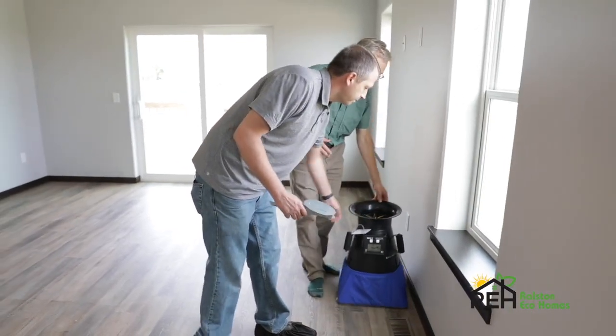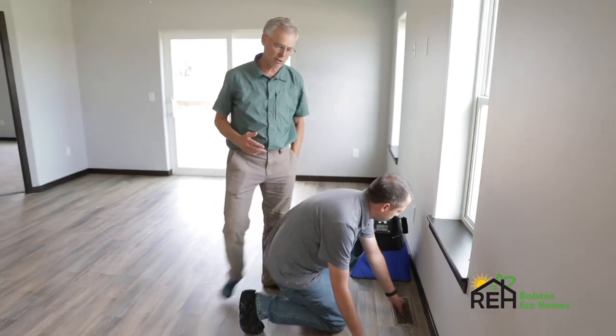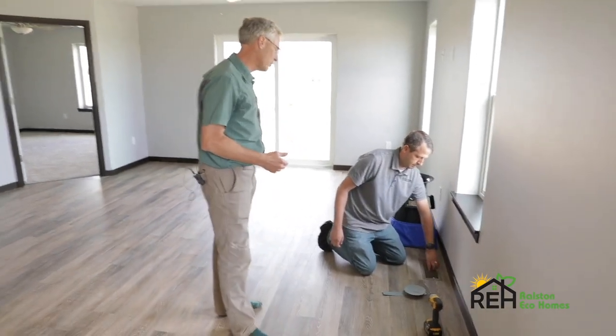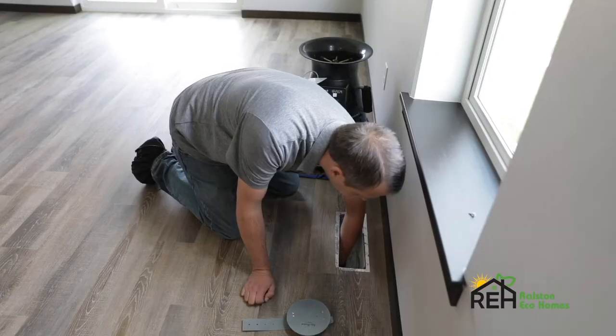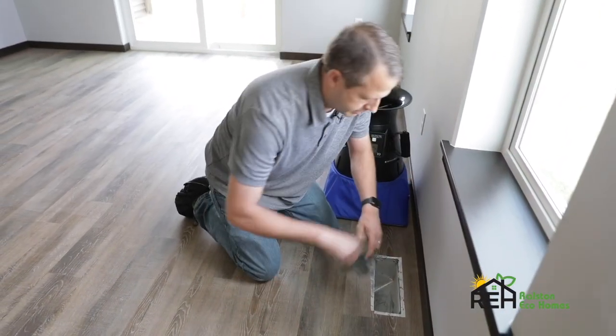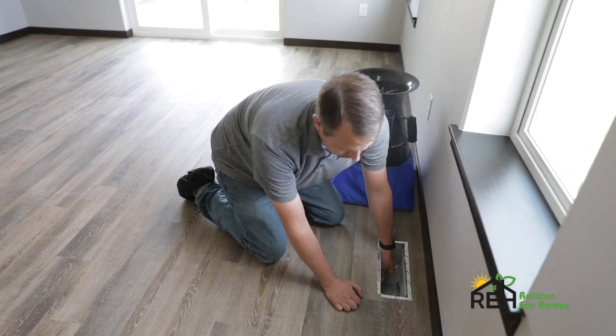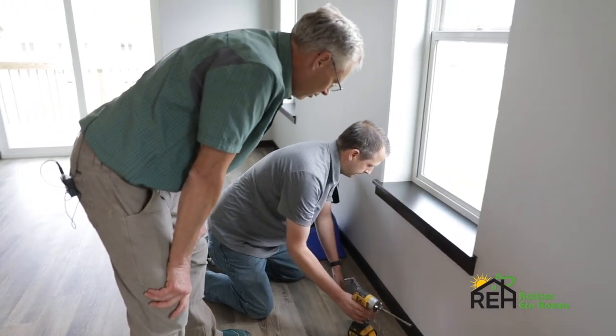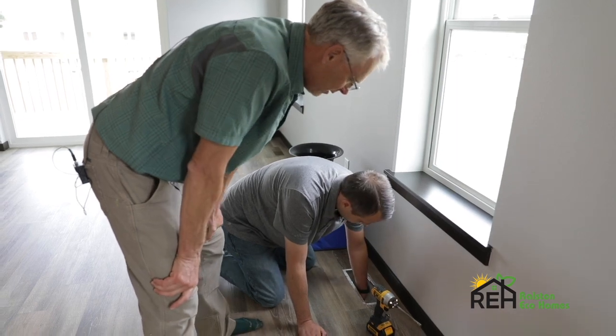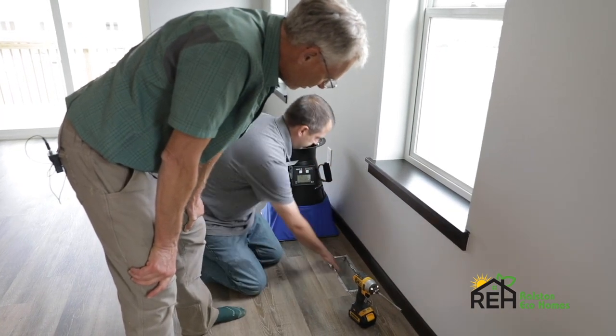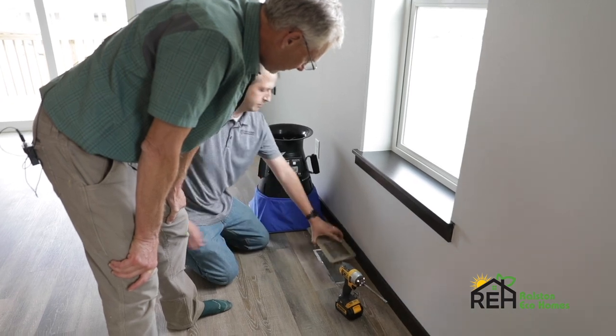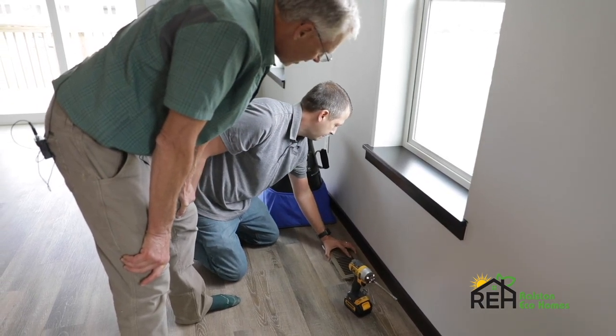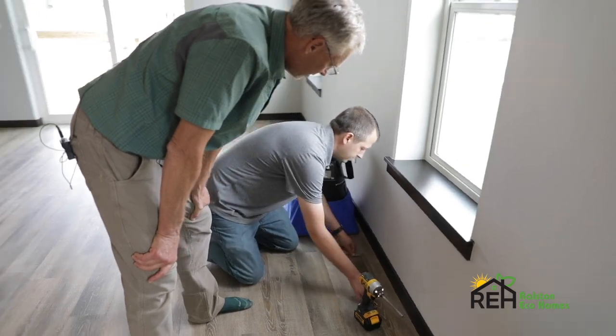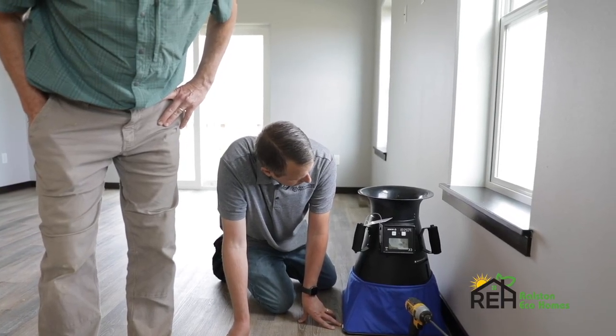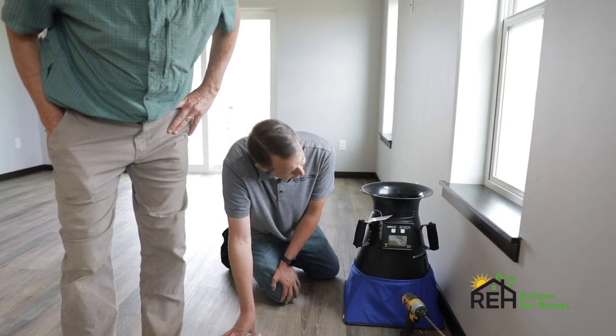And then what if this is off? So then there are two ways to do this. We could have installed a damper at the time of construction, but if we're coming into a situation where a damper has not been installed, then this is a retrofit. Yep. Okay, so that damper is sitting inside the duct. And then you're going to be able to open and close that to restrict flow from the duct. We always measure with the register back in. Yep, because that's the actual situation that it'll be in. So you've restricted the flow there. Looks like it's 55, 54.